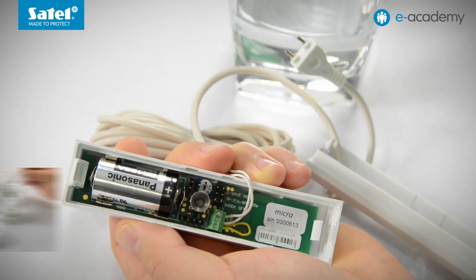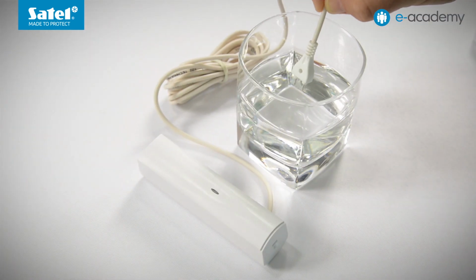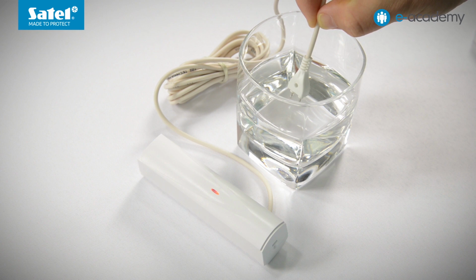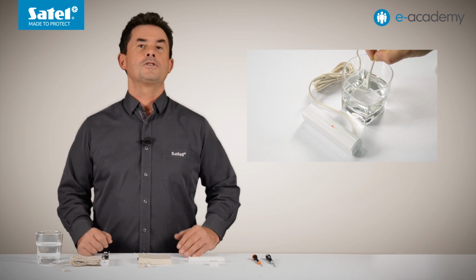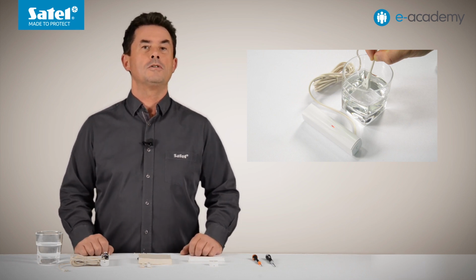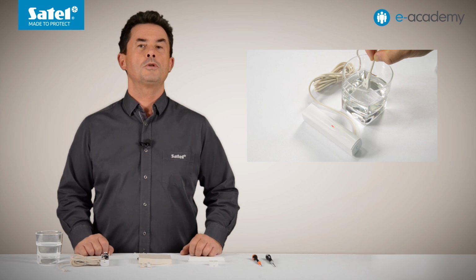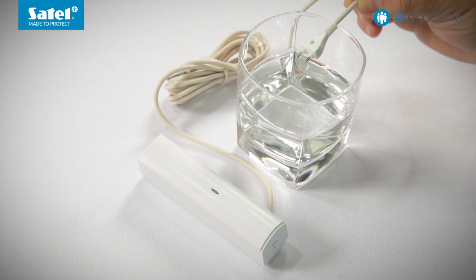Well, so far so good. To check the operation of the flood detector, immerse the probe tips in water. As you can see, the detector responds almost instantly to the simulated flooding. It should be noted here that the detector will only report the end of flooding a few seconds after the water level drops below the height at which the probe contacts are located.